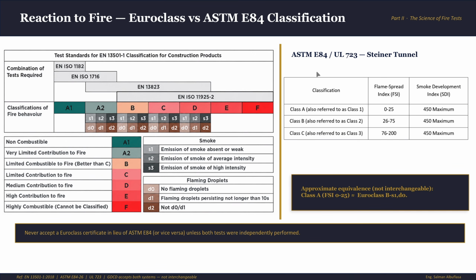ASTM E84 or UL 723. It is the American equivalent, but different apparatus, different fire scenario, and it's not interchangeable with the Euro class. So, the Steiner tunnel test is a 10-minute test that measures two things: how fast the flame spreads across the material, and how much smoke it produces. So there are two outcomes: the flame spread index and the smoke development index, the FSI and the SDI. And out of it come the three classes: class A, B, C, or 1, 2, 3. It depends.